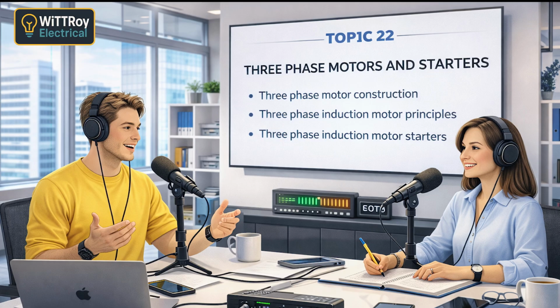What about losing one phase? Good question. In star connection, the motor usually can't start at all. And in delta? It may keep running, but current becomes unbalanced. So overheating again? Very quickly. That's why phase failure protection is important in industry. I don't see that much in houses. Exactly. That's why this topic feels unfamiliar.